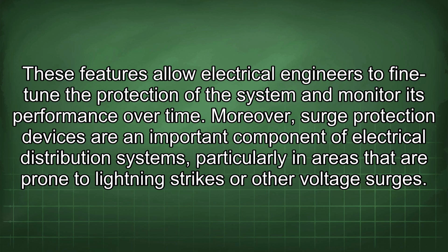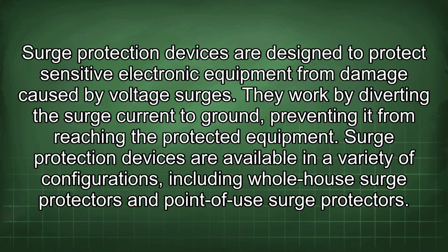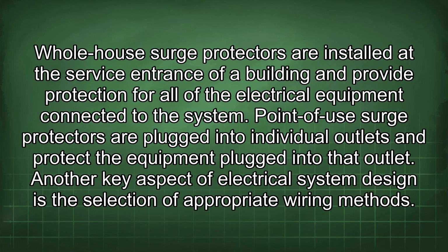Moreover, surge protection devices are an important component of electrical distribution systems, particularly in areas that are prone to lightning strikes or other voltage surges. Surge protection devices are designed to protect sensitive electronic equipment from damage caused by voltage surges. They work by diverting the surge current to ground, preventing it from reaching the protected equipment. Surge protection devices are available in a variety of configurations, including whole-house surge protectors and point-of-use surge protectors. Whole-house surge protectors are installed at the service entrance of a building and provide protection for all of the electrical equipment connected to the system. Point-of-use surge protectors are plugged into individual outlets and protect the equipment plugged into that outlet.